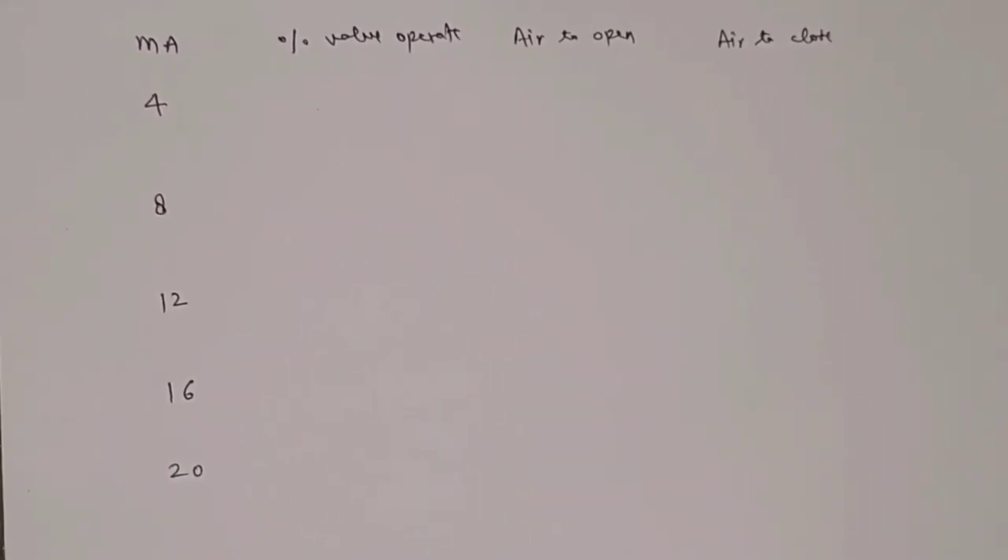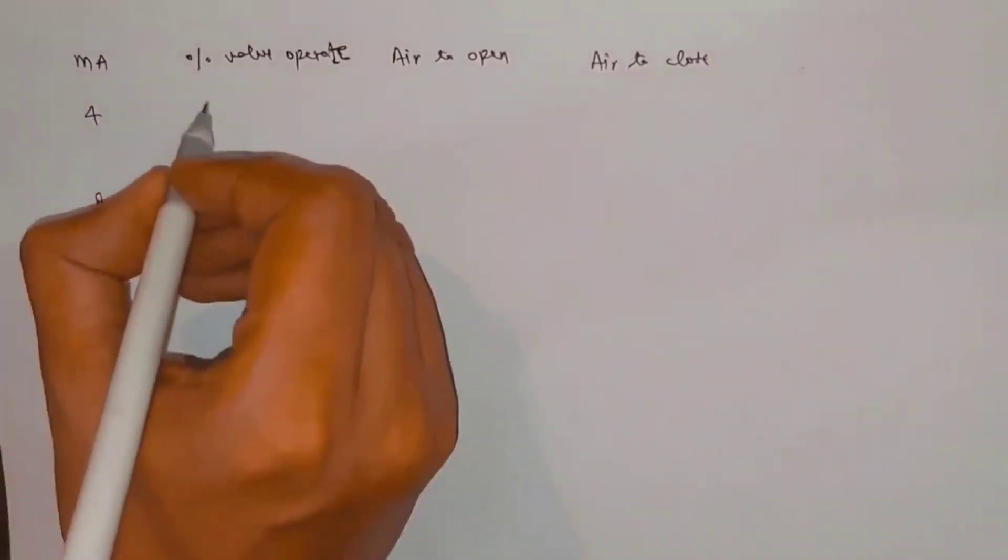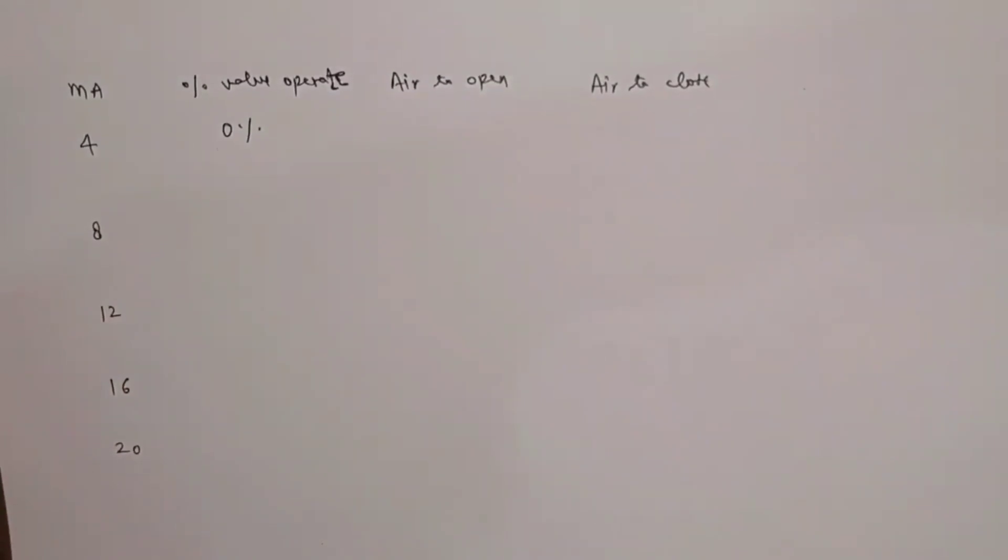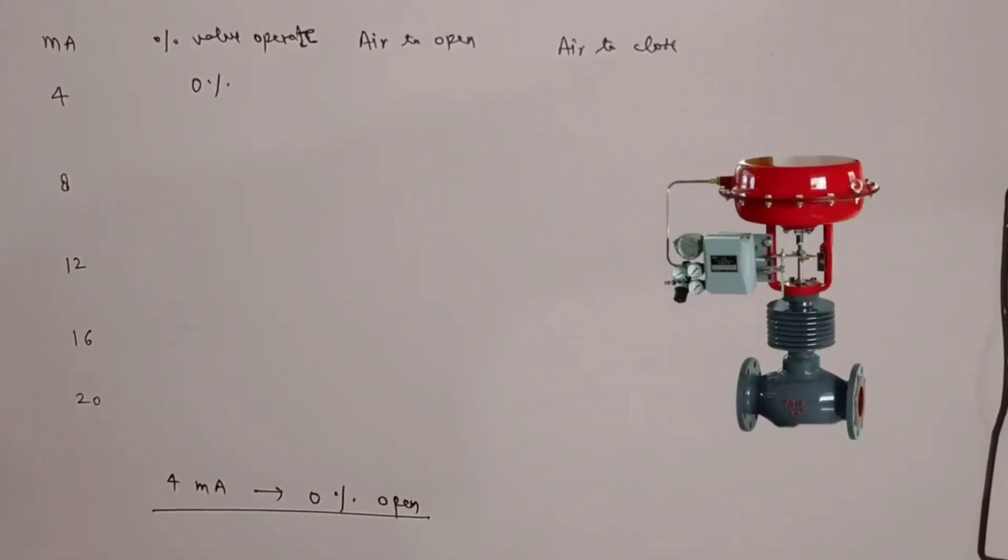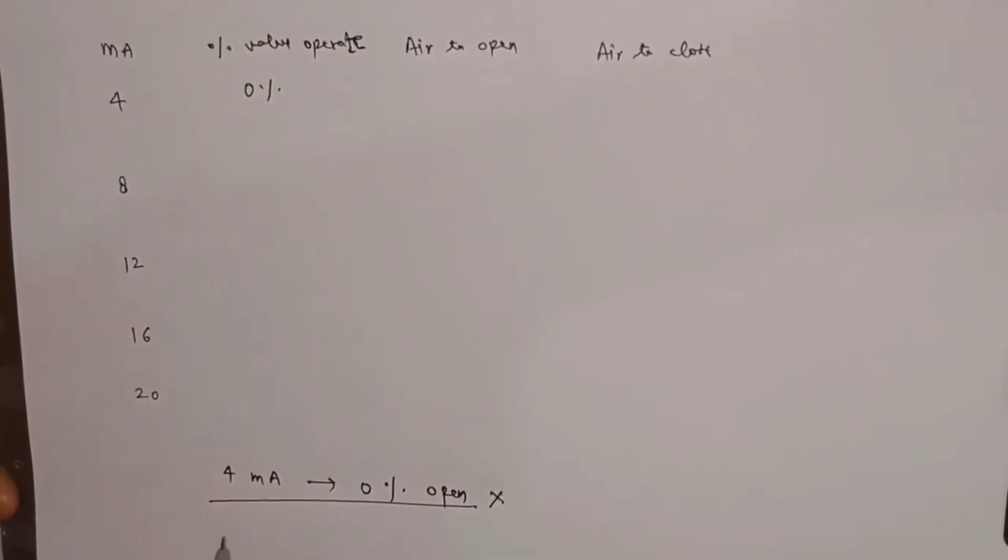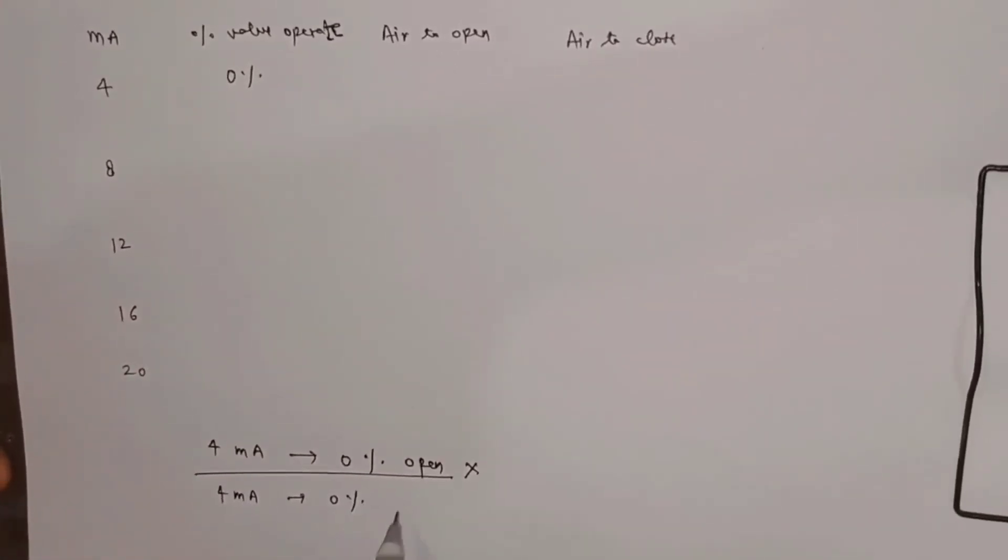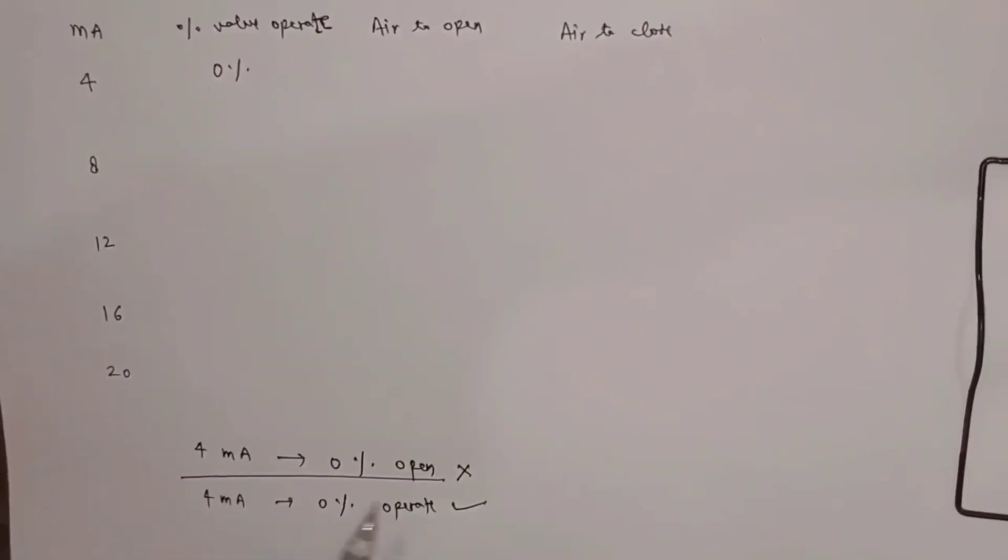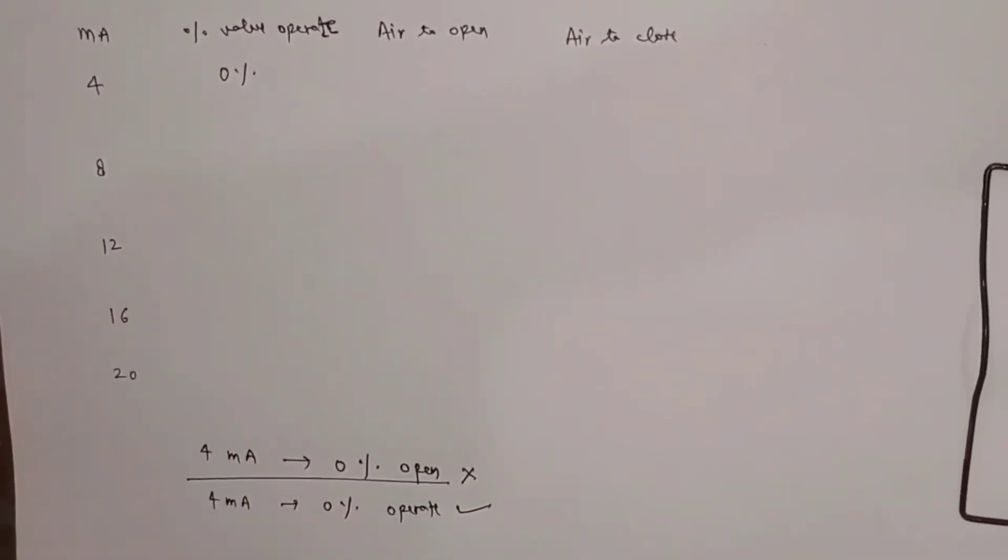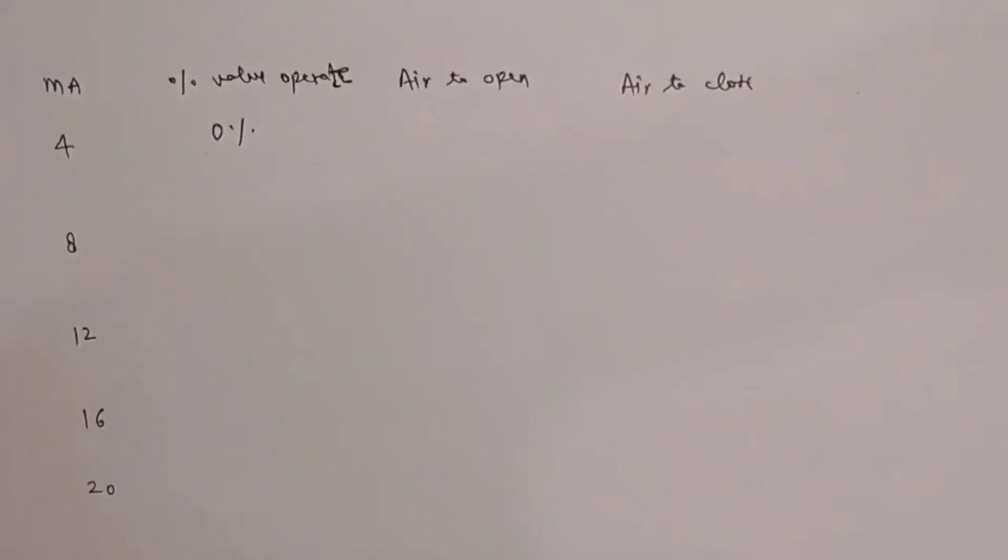Let's understand it further. Look friends, at 4 milliamps, valve operates 0%. Here, you need to keep one concept in mind. At 4 milliamps, many people think that valve opening is 0%. But this is not applicable on all control valves. You can say it like this: at 4 milliamps, control valve will operate 0%. So this sentence is correct. Not that at 4 milliamps the valve will open 0%. With this concept, you will understand everything.